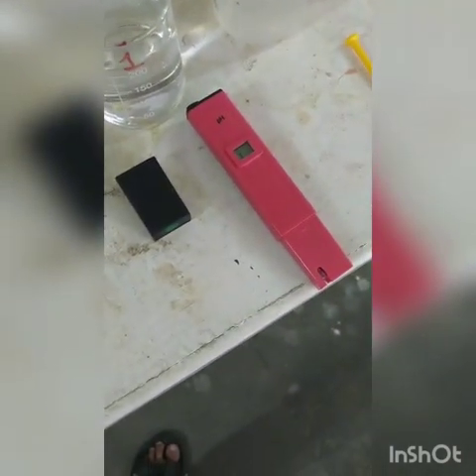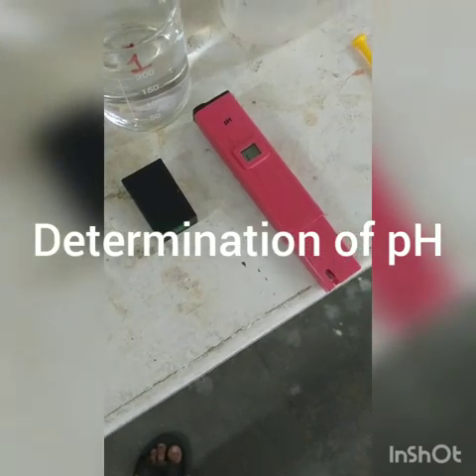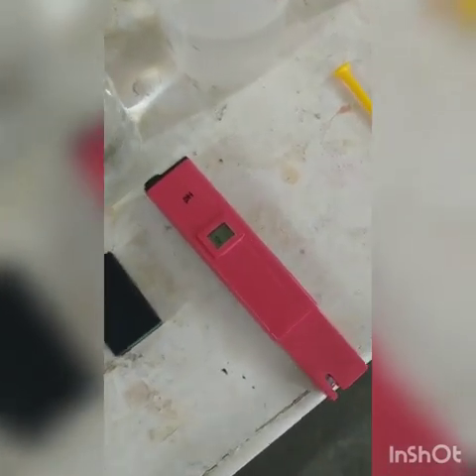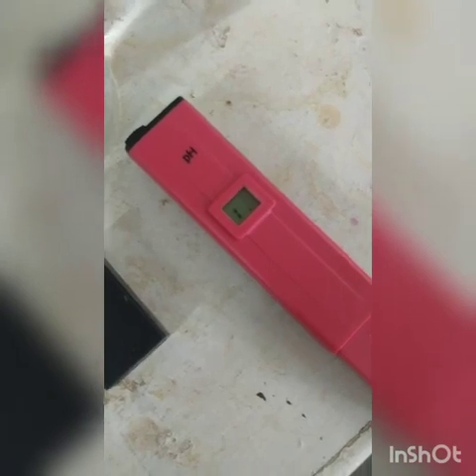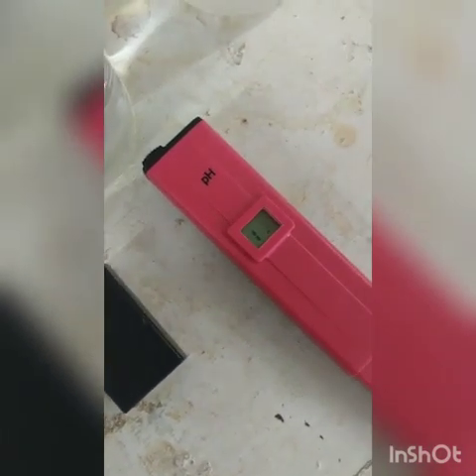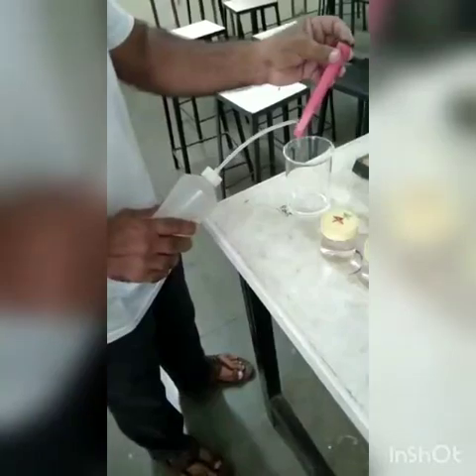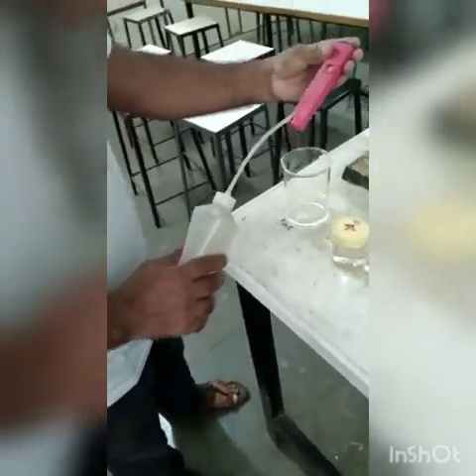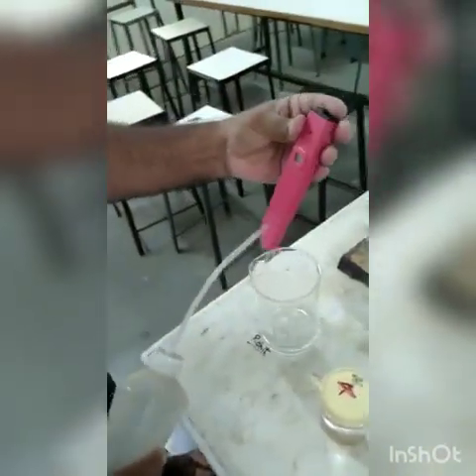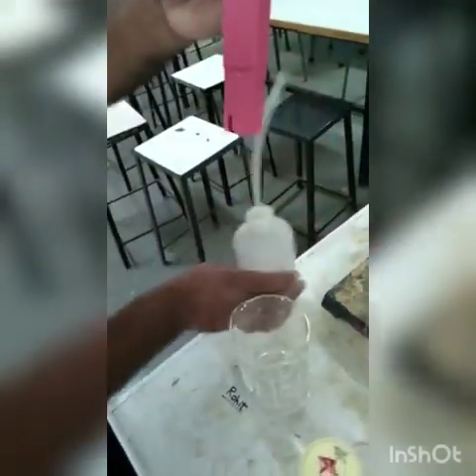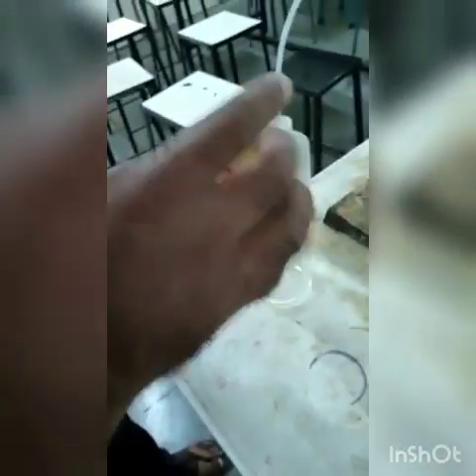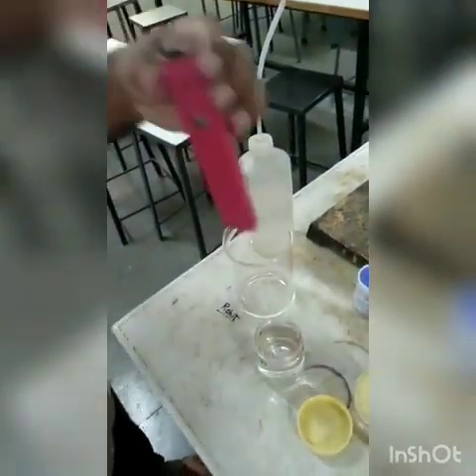So now we will calibrate the instrument, for which we have to wash it every time with distilled water. So now we will start with the calibration part, and once each calibration is done, we will show you these values. So now we are starting with the calibration part. Before calibration, we need to clean the pH probe with distilled water. So we have cleaned it with the distilled water. Now we are calibrating it with the standard solution of pH 4.